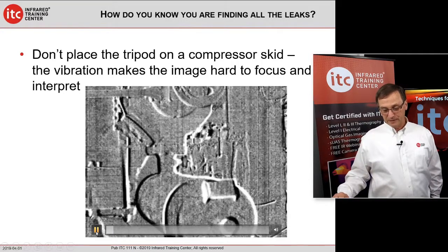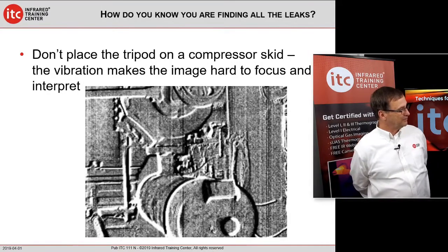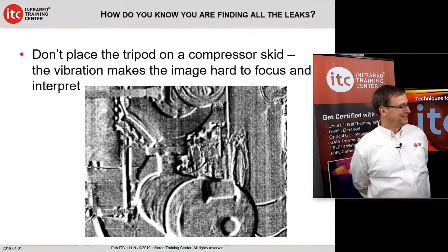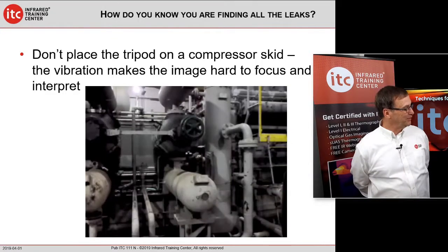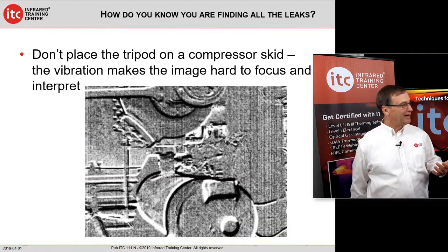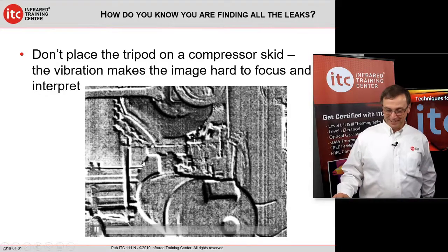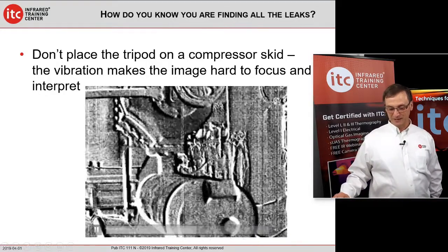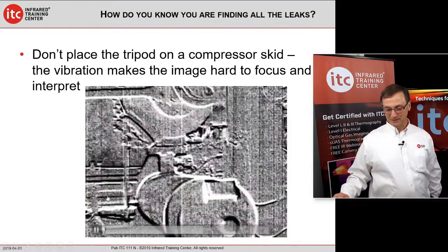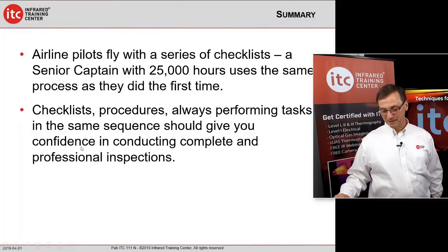And a couple other things here. Do not, if at all possible, put your camera tripod right on the compressor skid. I mean, these things are big and noisy, and they vibrate a lot, and everything just shakes. And so particularly with a high sensitivity mode, you can get a jiggly video, and you go, well, wait a minute, what's gas and what's not? And so there was a little gas leak sitting back there. That's all that was off that flange, I believe.